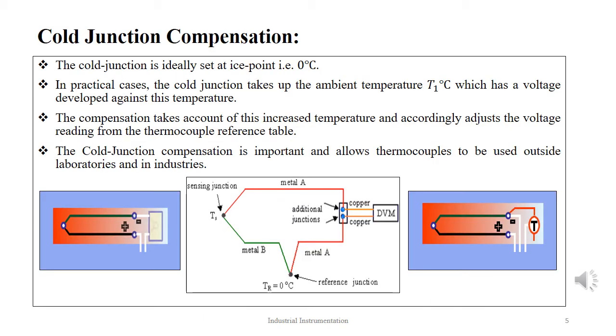The thermocouple operation does require a stable voltage reference and some form of ice point or cold junction point. Since the thermocouples measure temperature differentially, the cold junction temperature must be a known temperature to correctly determine the differential temperature. But due to the operational limitations and errors, the cold junction temperature rises above the ice point. Therefore, the output voltage needs to be compensated to account for the voltage created at the non-zero cold junction. The process of this voltage compensation is called cold junction compensation.